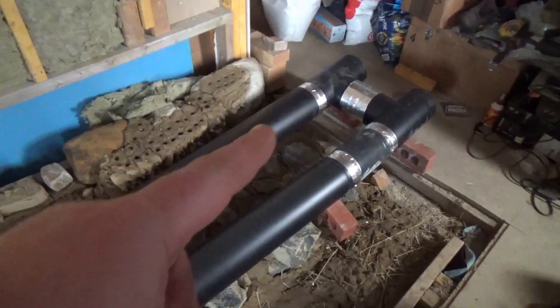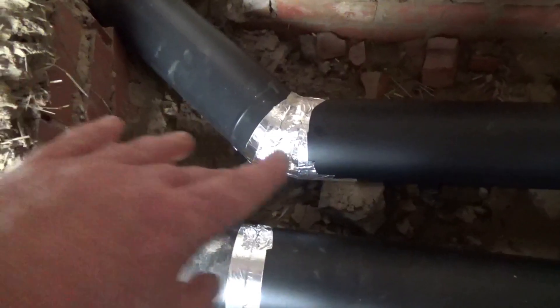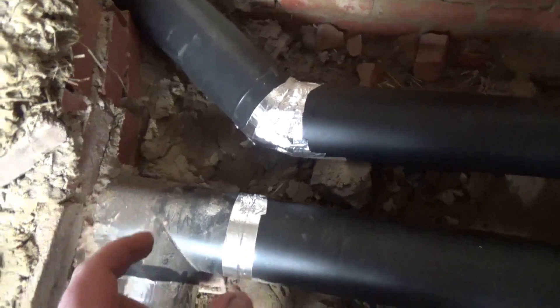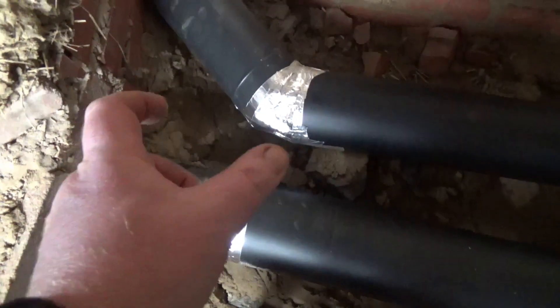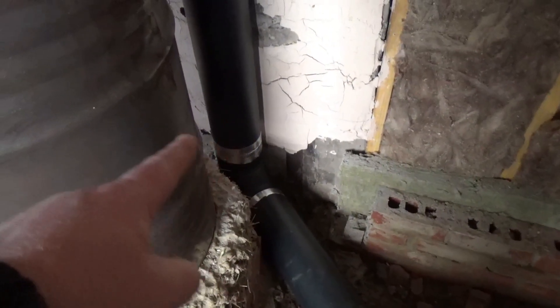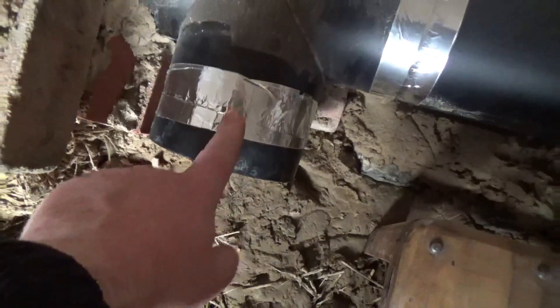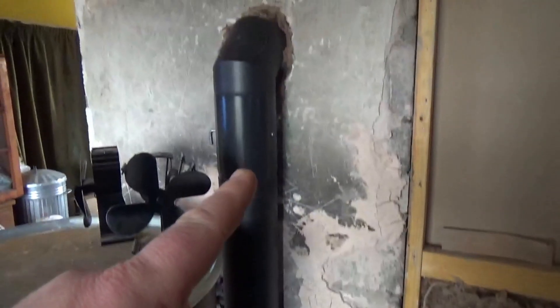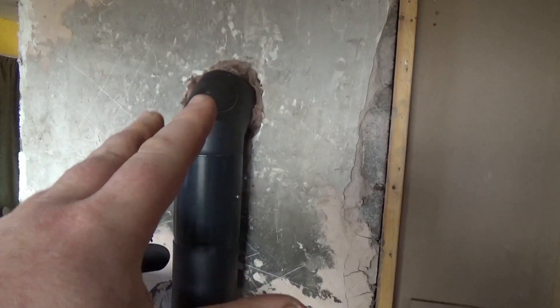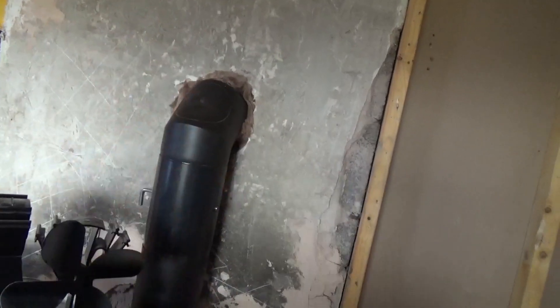We taped up all the really leaky joints — that is three layers of aluminium tape, nothing else. There's nothing solid inside there, it's just aluminium tape, and there's quite a gap, probably four or five inches down in there — it's a significant gap. These joints here aren't even taped up; you can see there's a few that aren't. In fact, this wasn't even taped up the first night we ran it. Up the top, that join isn't taped either, and around the hole itself we couldn't do much because this still needs to be moved and adjusted. I jammed loose insulation around it just to restrict the flow a little.